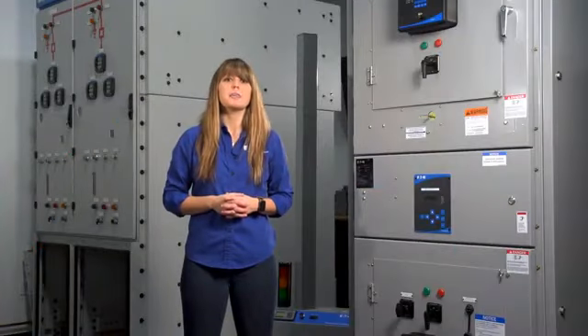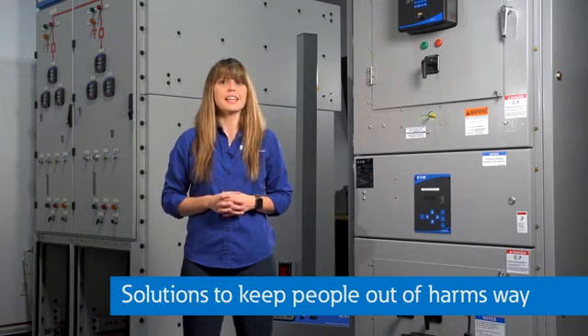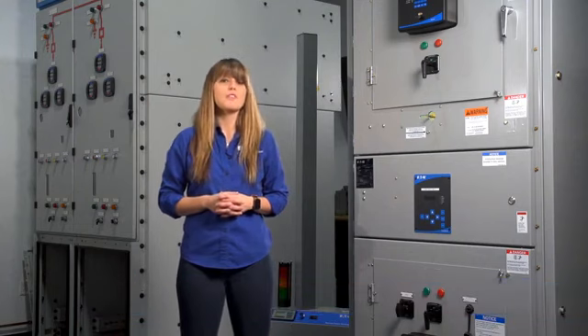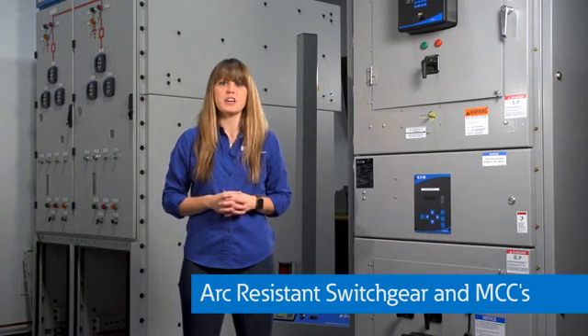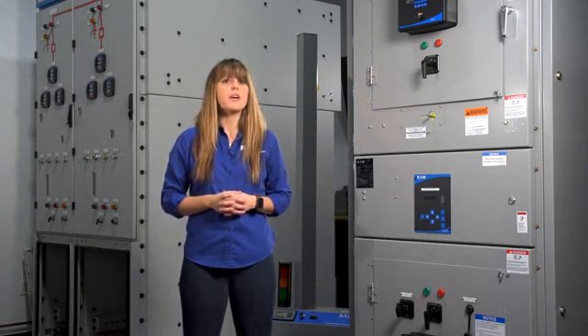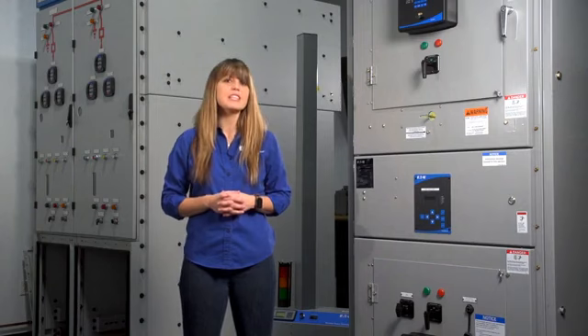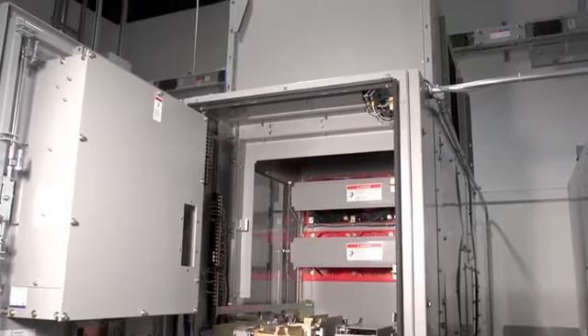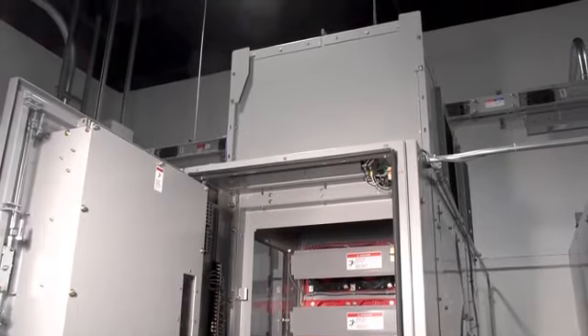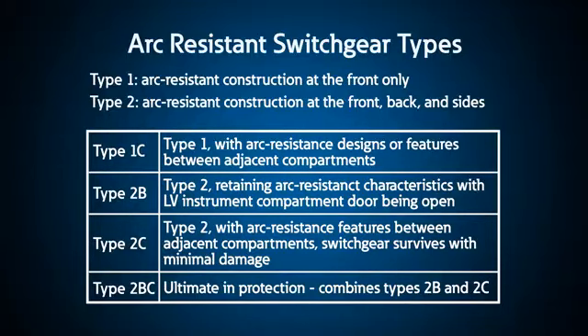Now, switching gears a little bit, let's talk about arc flash solutions that keep people out of harm's way. The first solution is called arc-resistant switchgear and MCCs. In general, arc-resistant equipment contains and redirects arc energy away from personnel and the facility out of the top of the equipment. The most common is called Type 2B, meaning you can walk all the way around a section of equipment, and if an arc flash occurred inside, you wouldn't be hurt because the arc flash energy would be exhausted or dissipated out of the top, and in some cases through a plenum outside the room or area where you are working.